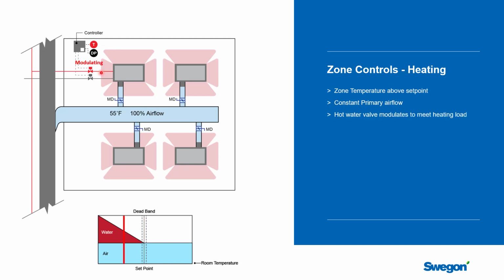And then, of course, as the temperature drops in this space, it gets colder outside, or you have less internal heat gain, we're no longer at the set point, we're below set point. And so the controller will start to modulate this hot water valve to match the load requirements of the space. And so it'll be able to vary the flow. And as it does that, that flow will go to all 4 beams so that we get even heat all through this zone. And that will move that back up into the dead band and satisfy the space.